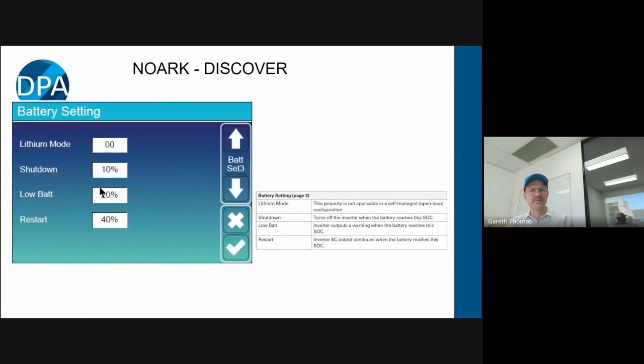You can then set the shutdown, restart, and low battery warning voltages. Again, these are independent of what the battery is going to do - the battery is going to shut down regardless. I've taken one down to about 1% before, but you wouldn't want to design your system that way. This is what the inverter will do, and it's not specific to Discover - this applies to any managed battery with a NOARK inverter.